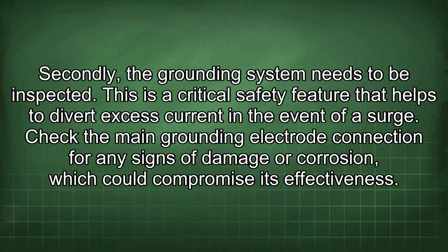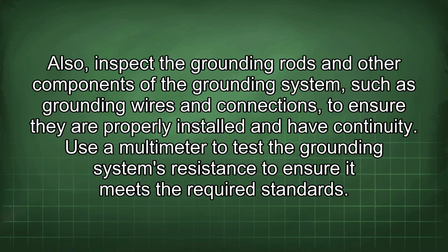Secondly, the grounding system needs to be inspected. This is a critical safety feature that helps to divert excess current in the event of a surge. Check the main grounding electrode connection for any signs of damage or corrosion, which could compromise its effectiveness. Also, inspect the grounding rods and other components of the grounding system, such as grounding wires and connections, to ensure they are properly installed and have continuity.